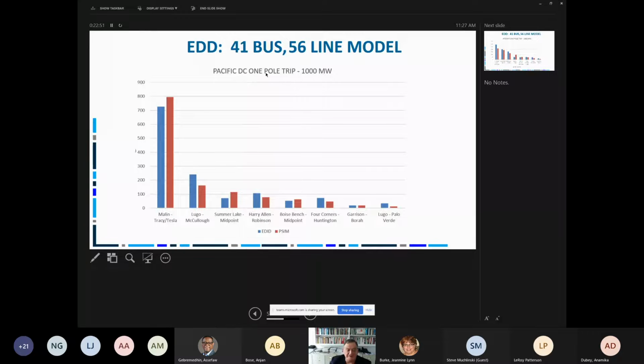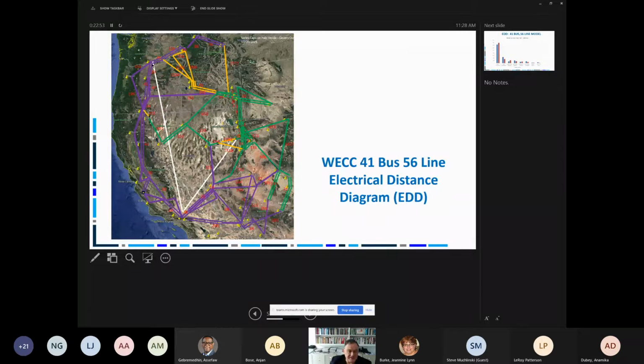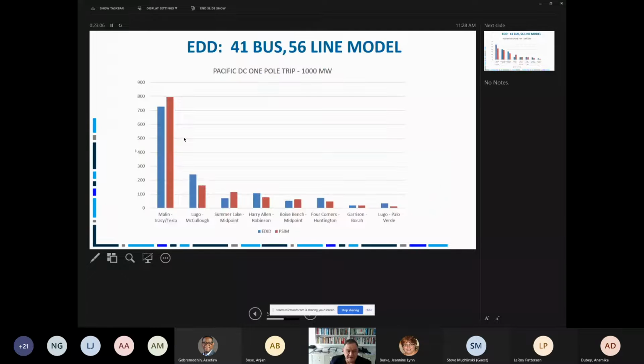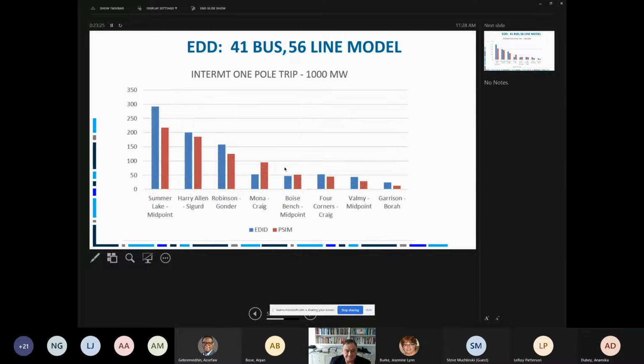Okay, so we've got two DC lines in this one. We've got the Pacific one, typically taking about 1,000 megawatts, and then the Intermountain one, about 2,500. And if we trip this line, this is the predicted flow from the electrical distance diagram in blue versus the full detailed power simulator model. And so it's pretty close, okay? So the idea is to come up with a reduced equivalent so that we can do the very detailed simulations going forward.